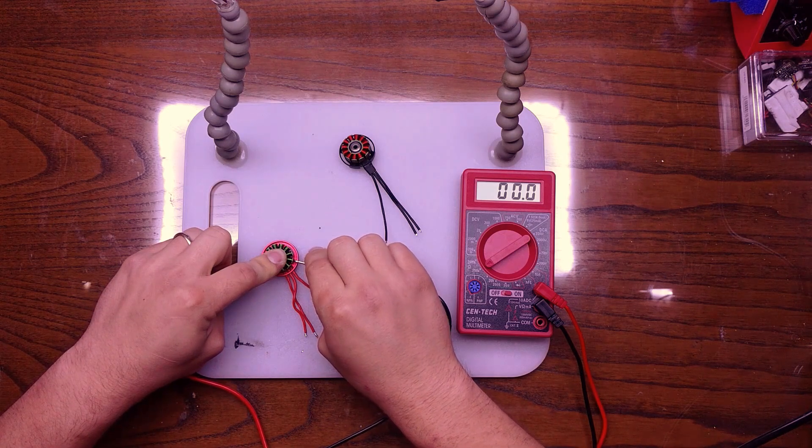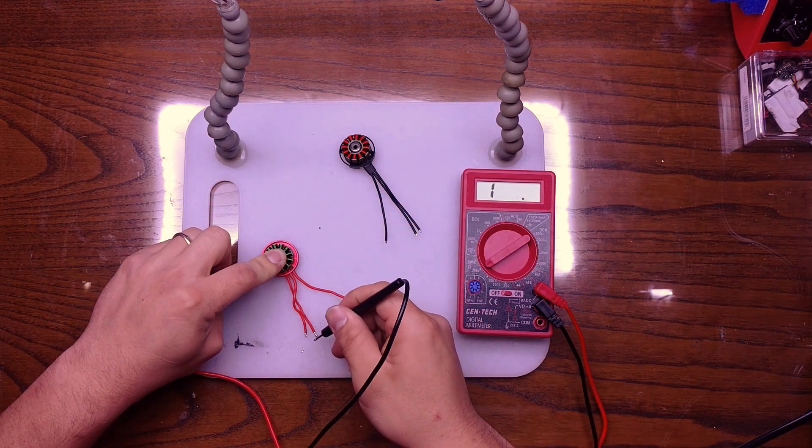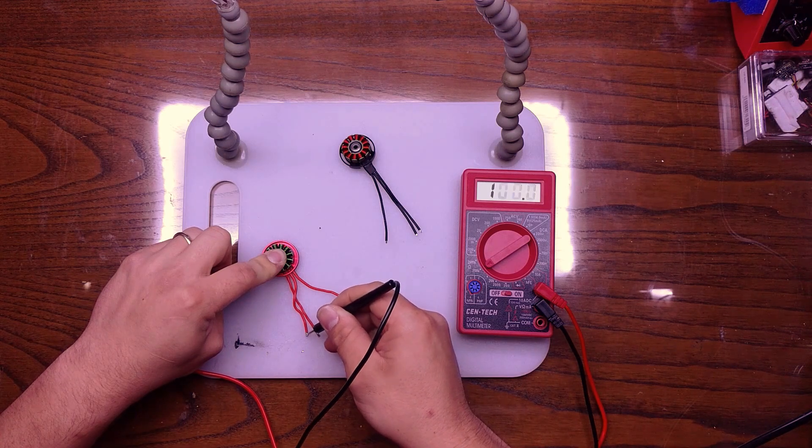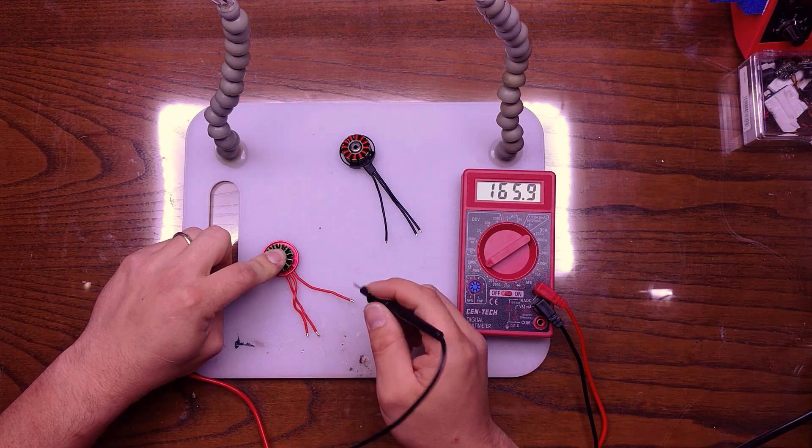Okay, so there we go. We have a connection. I'm going to take this one and just touch one of the leads. And as you can see, this stator is bad. It has a short.